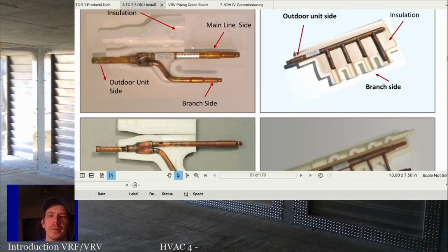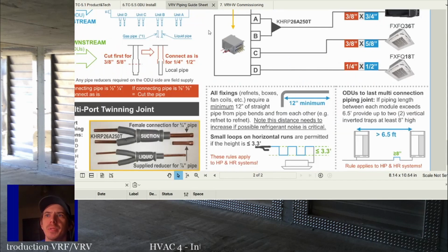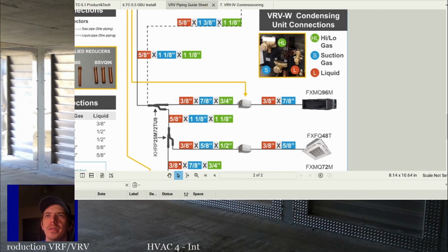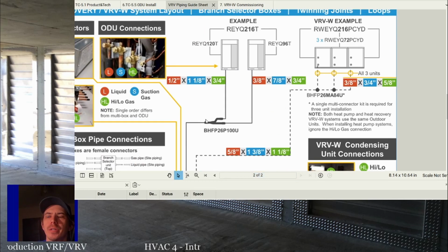All right. And I had a better picture. Here we go. All right. So you have these special fittings. So basically, VRF is the only system I'm really aware of where you will see the piping split like this. So if you look at it, the piping from the outdoor units converges together. So if this is a liquid line, these two liquid lines will come together and then they'll join to continue through the system. And then your suction lines will come out. There's actually three of these.